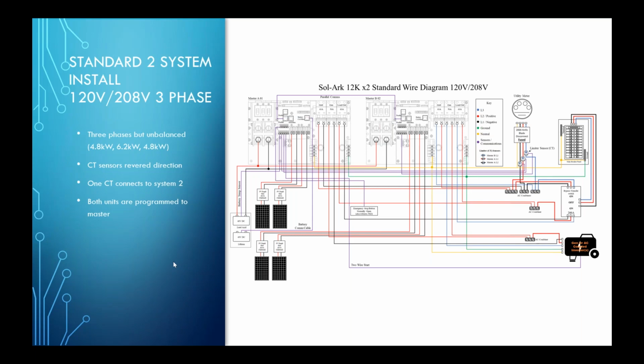But here you'll have the L1 and L2. Those need to be labeled very carefully and correctly because we need to make sure the internal wiring is consistent with the phasing that's coming from the utilities. So 3-phase is definitely an interesting wiring setup for the system. If you are in a 2-system setup and you have questions, please reach out. We can go into more details. But really, the hardest thing is making sure everything's labeled correctly, so that it travels up the line and there's no phase imbalance or out of phase condition down the line. So if you have questions, give us a call.